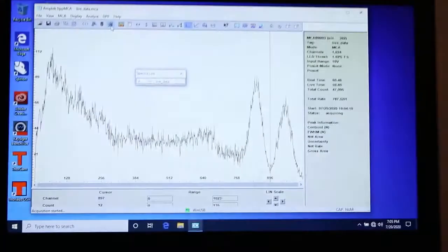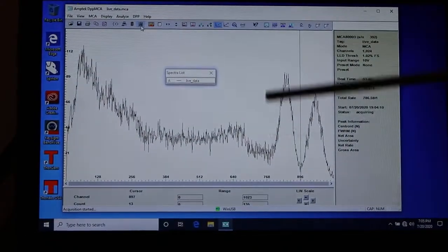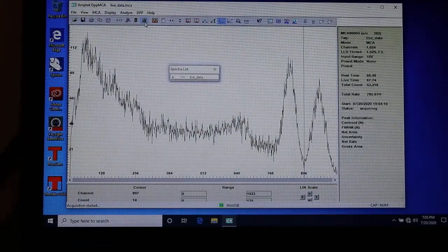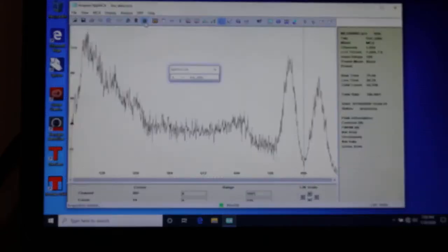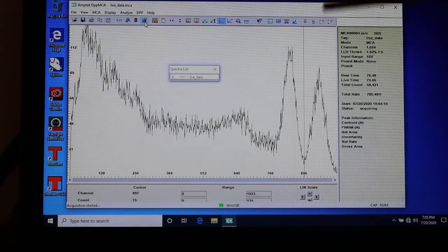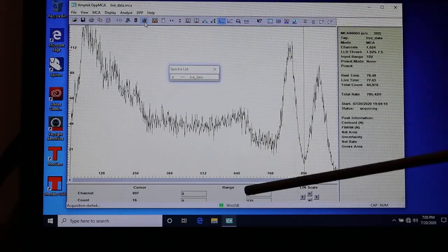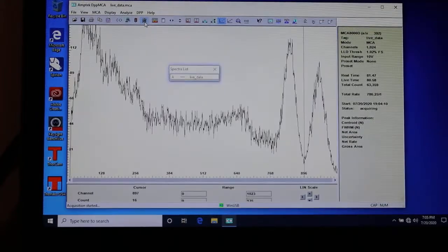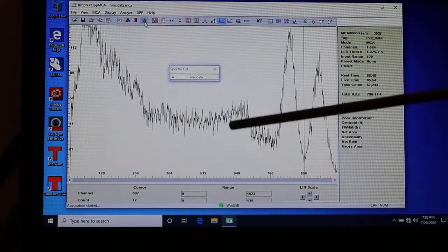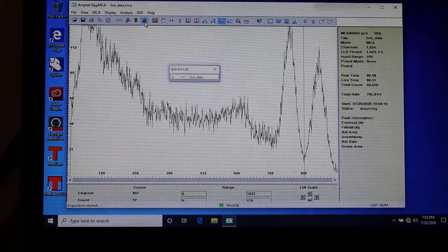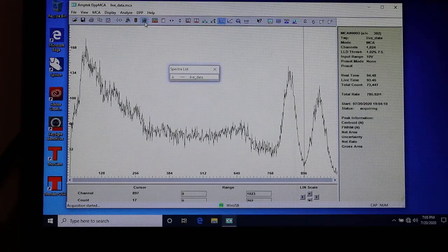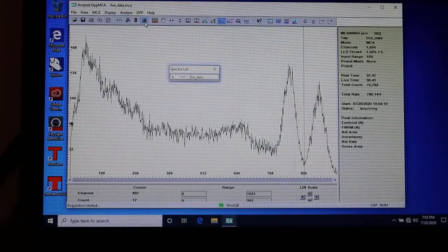What that says is, no matter what, we know cobalt-60 is going to occupy these channels, and everything else will fall in between. By not touching the amplifier, we have some commonality in these channels that will exist among all the sources we'll put on the detector. Cobalt-60 will appear about here, cesium-137 will be about here, sodium-22 will be here, as you'll see. So when I see the cesium-137 peak rise up over here, I'm not going to turn the amplifier gain up to move it over here to use all the channels just for that spectrum. I'm trying to get a common channel set for all of these gamma rays so I can get this x-axis calibrated into energy.